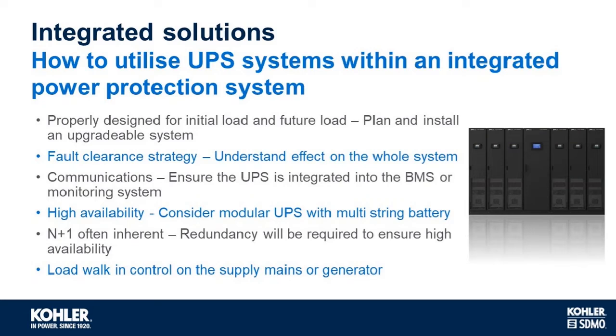Another thing that we must consider in the whole strategy is the fault clearance of not just the UPS, but obviously of the generator, and how the UPS will handle the downstream faults and how that translates onto the generator systems as well. Importantly, it's very important that we understand that the UPS is available, and this is quite often done by integration into the building management systems and monitoring systems on site, because we need to make sure that that system is operational. That all comes down to the availability. And availability is very critical and is a big subject. But what we want is the highest availability for the type of load we're running. And we can consider different types of UPSs and we run through those to try and make sure we get that availability we want.